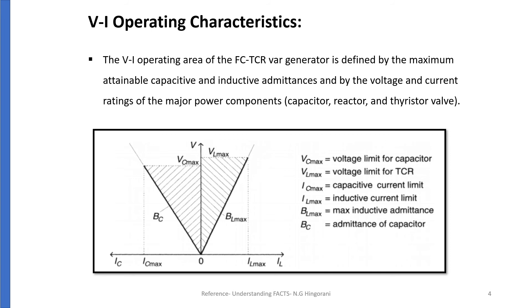The VI or operating characteristics of FCTCR are defined by the maximum attainable capacitive and inductive admittances, and by the voltage and current rating of the major power components — that is, the capacitor, reactor, and the thyristor valve. Here we can see the operating area of FCTCR: maximum capacitive voltage, maximum inductive voltage, maximum capacitive current, and maximum inductive current. BC is the admittance of the capacitor and BLmax is the maximum inductive admittance of the FCTCR. FCTCR operates within this range as shown in the shaded area.